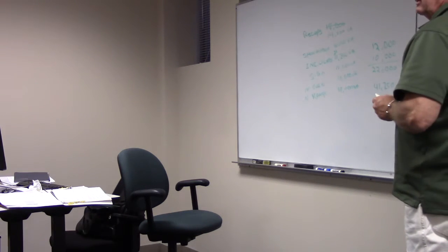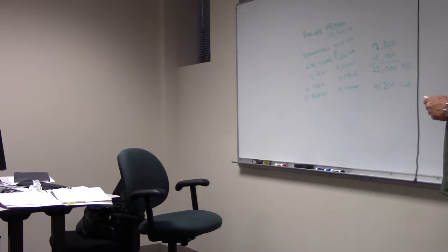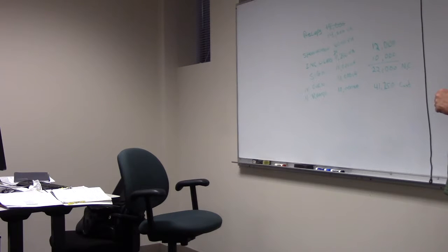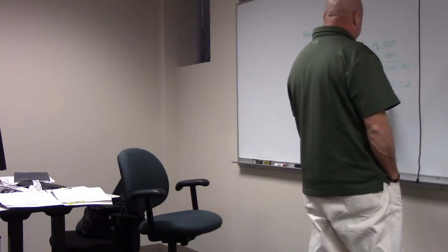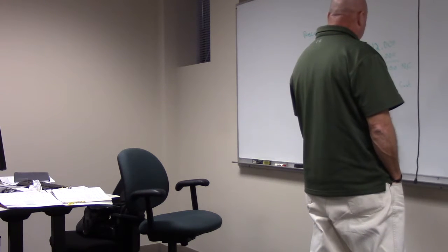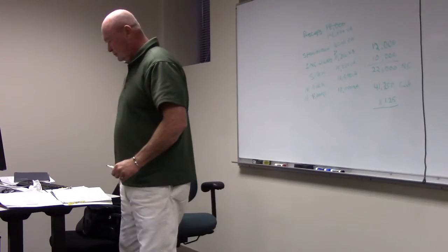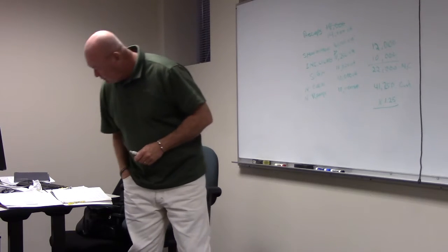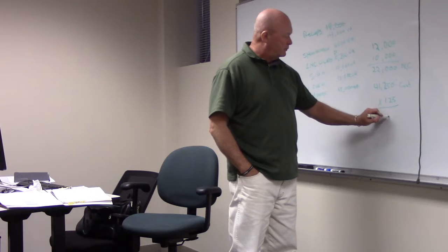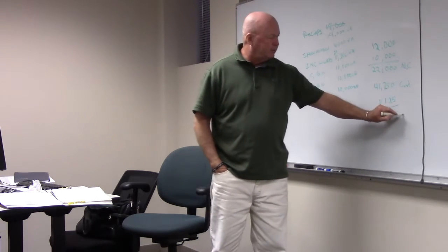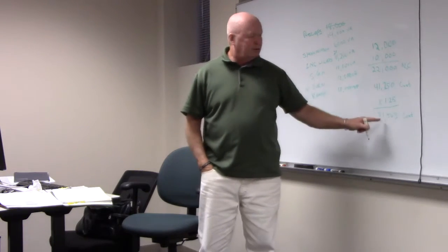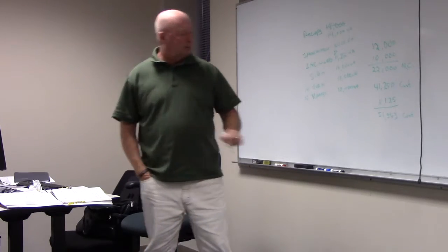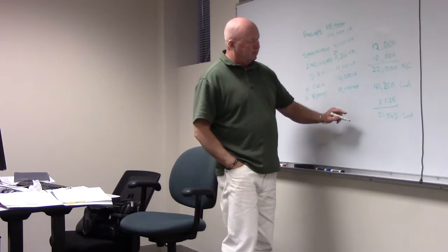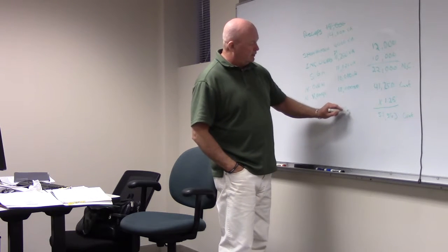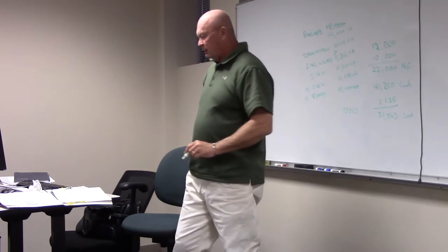All right. Continuous load, what do we have to do with anything that is non-continuous load? No. But we have to do something to continuous load. 125 percent. How much does that equal? 51,563. Yep. So that's our continuous load. That's our non-continuous load, 22,000. So what are we going to do with those two numbers? We're going to add them together, aren't we? Yes. We're going to get 73,563. Is that right? Yes. Okay.